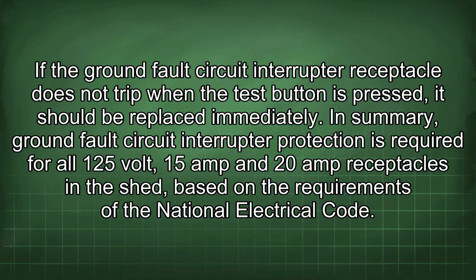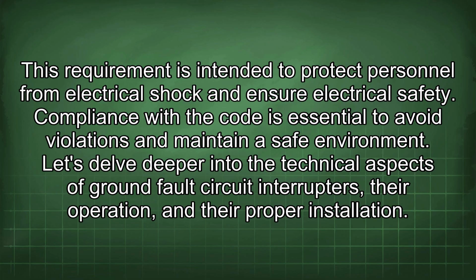In summary, ground fault circuit interrupter protection is required for all 125 volt, 15 amp and 20 amp receptacles in the shed, based on the requirements of the National Electrical Code. This requirement is intended to protect personnel from electrical shock and ensure electrical safety. Compliance with the code is essential to avoid violations and maintain a safe environment. Let's delve deeper into the technical aspects of ground fault circuit interrupters, their operation, and their proper installation.